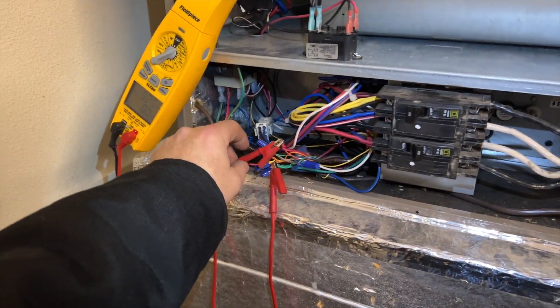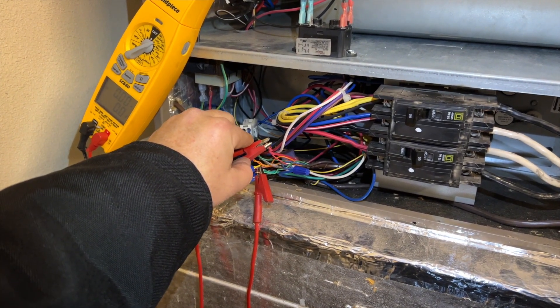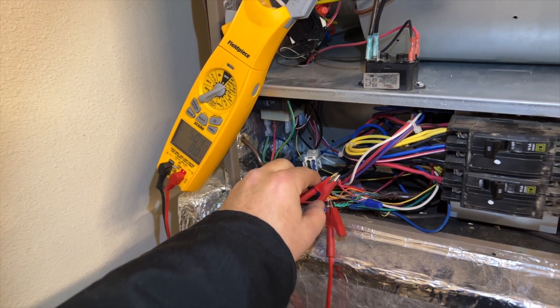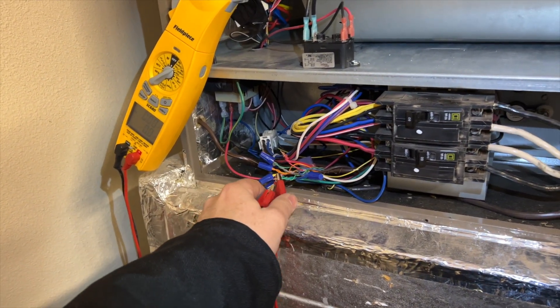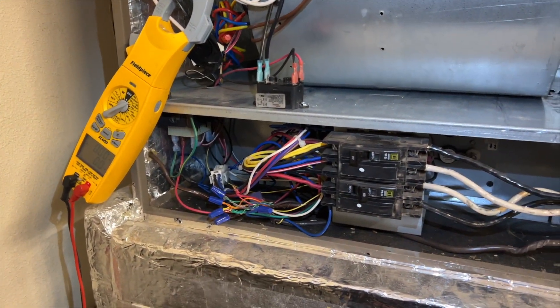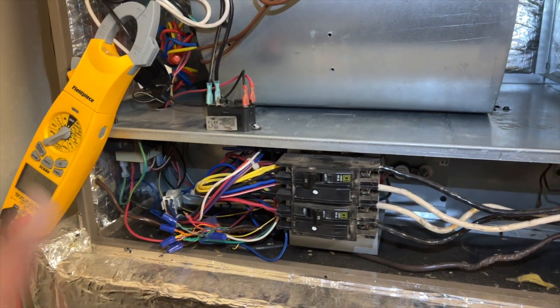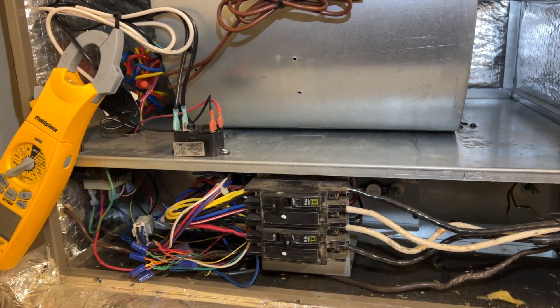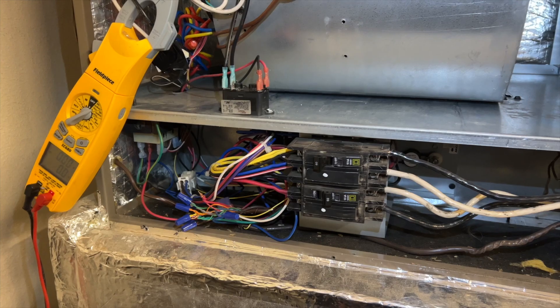Now that I know it works and it's spinning the correct direction, I'm going to clean this up, mount everything, and make it safe. Just making sure it turns on and off — cool. Checking run amps: probably about three to four with the door off, so it's a little high right now, but that's expected. Anyway, I'm pretty happy with these results. Once we get the OEM motor, we'll come back and install it. I was able to not hack up all the wires, which was nice. Hopefully this helps — thanks for watching, like and subscribe, hit the bell, follow me on Instagram and Facebook.